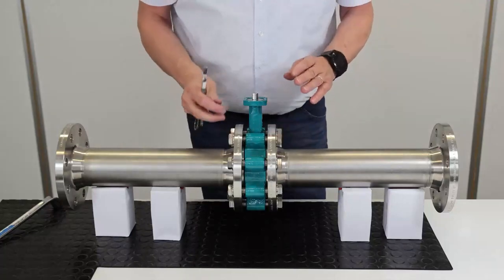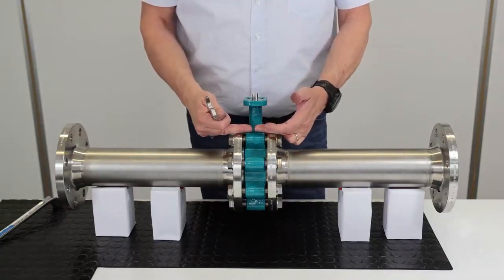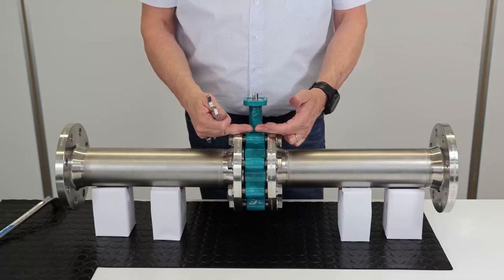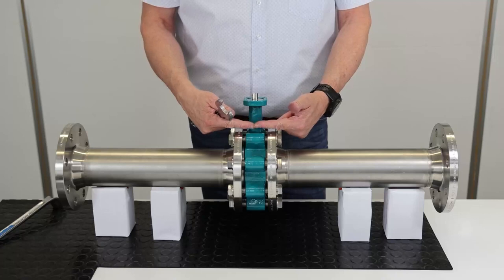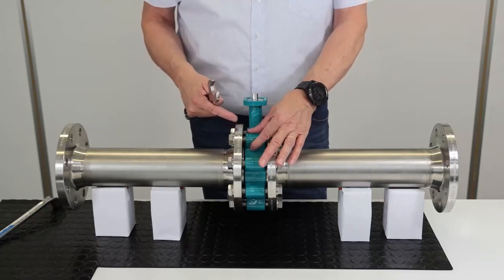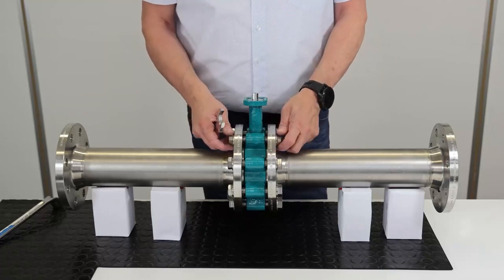It is very important to make sure that the length of the screws is according to the documentation, otherwise they might touch in the middle and then they risk breaking the ear of the body apart. If they are too short, there is a risk that they rip off the threads.